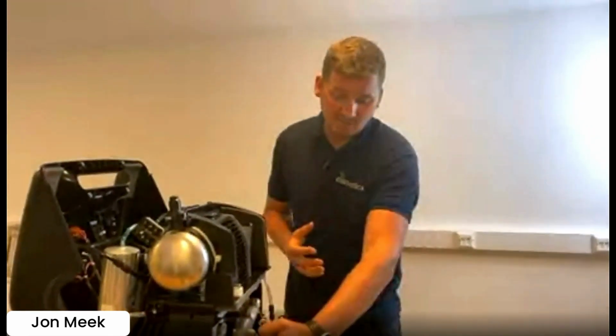Absolutely, it's a great question. So for the manual side of it, we have a maintenance manual. The maintenance manual is available from ourselves. So anyone that requests it, they can request the manual, and it gives intervals. But again, for us, we stipulate different timing. So I would say 2 years for your filters, but it does depend on environment. So it's more the fact of when to check things. It more is if you check your filters, your flows. It's all in the manual with all the breakdown of 2-year checks, 3-year checks, and even down to a compressor service. But again, it all relays back to looking after the machine, and the filters and the flow rates will almost determine when you need to change things as well.